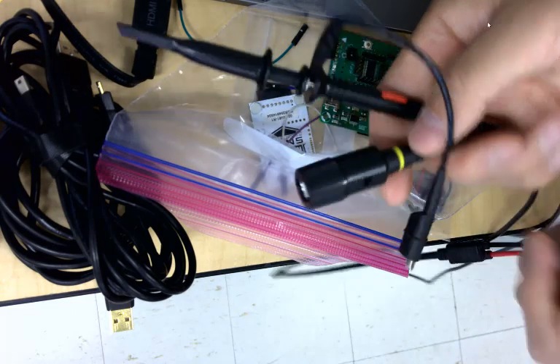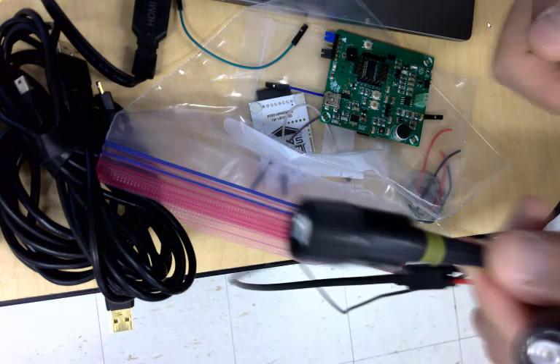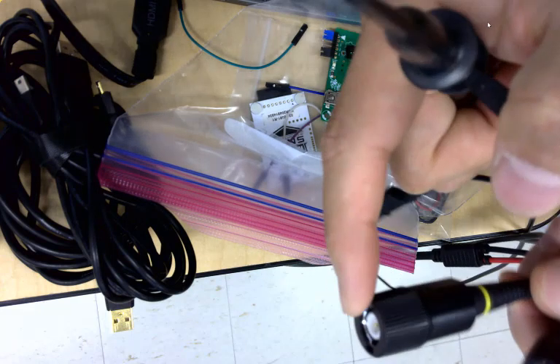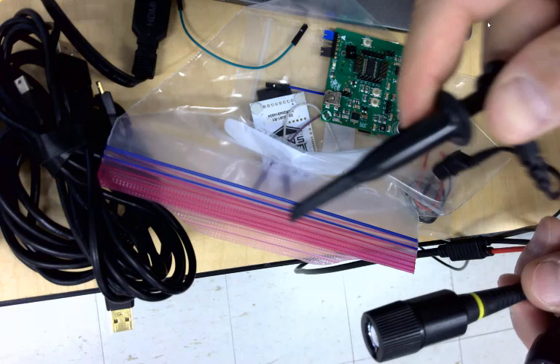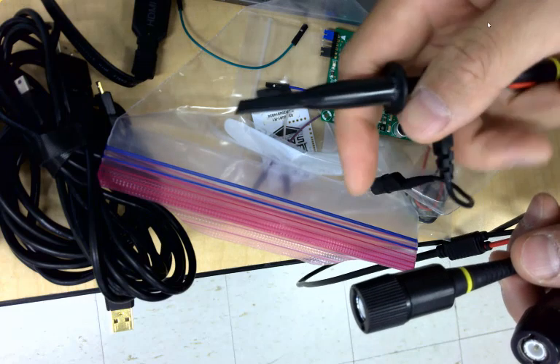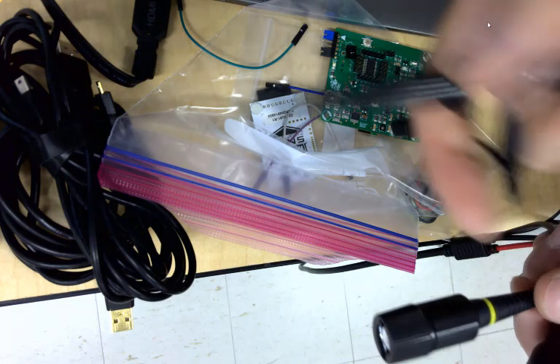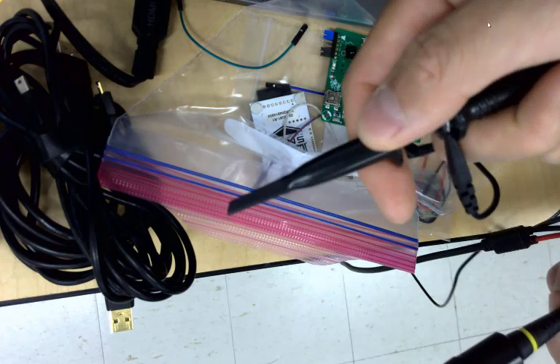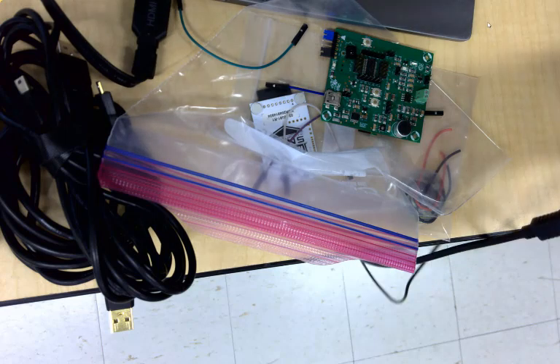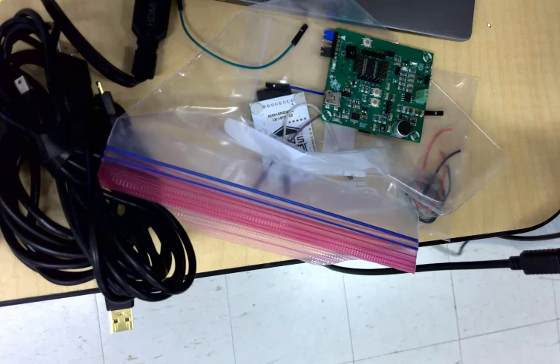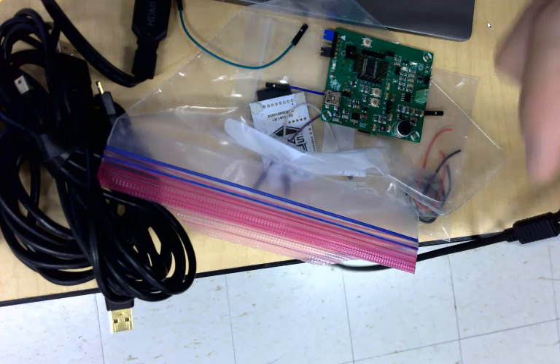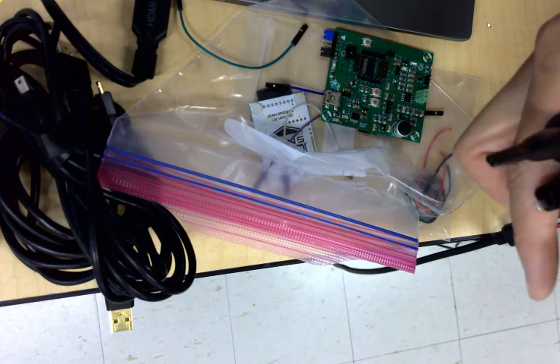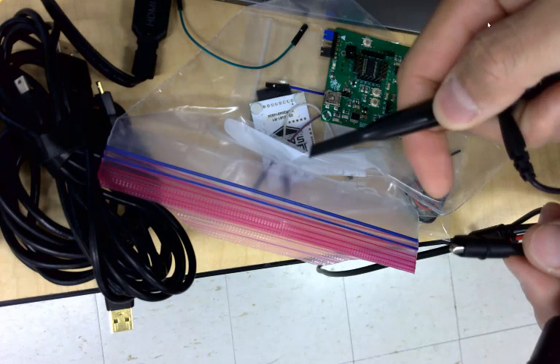Okay, and the second thing, usually you connect this connector to the input of the probe of the oscilloscope, and this one to the calibration signal of the oscilloscope. I believe most oscilloscopes have the same functionality. So connect to a standard pulse. It's usually 1 kHz with 5 volts. It's a standard waveform, not getting distorted or anything. Just a standard, strong, solid digital signal, 1 kHz, 5 volts oscillation. You probe that signal on the oscilloscope, and send it to the input.